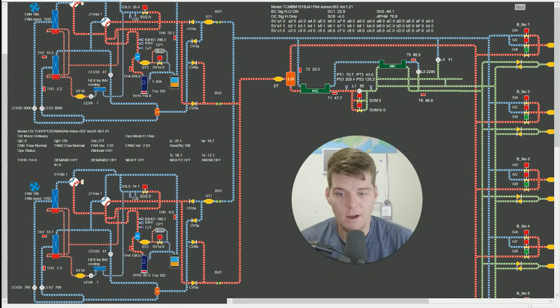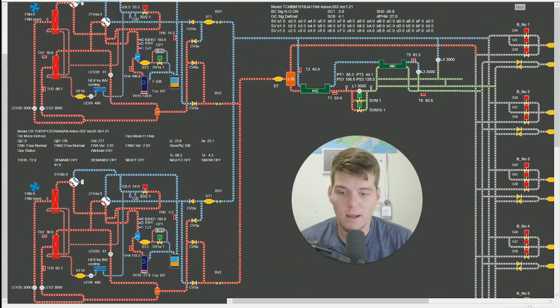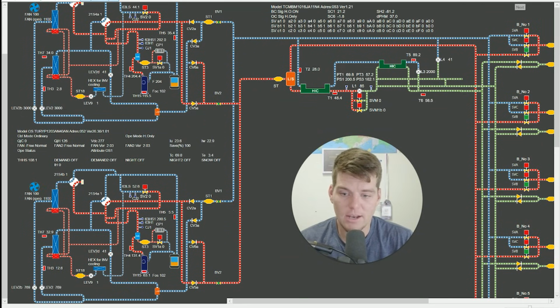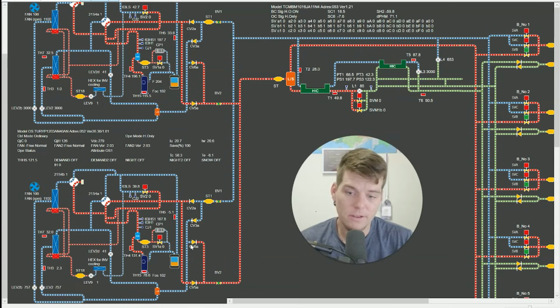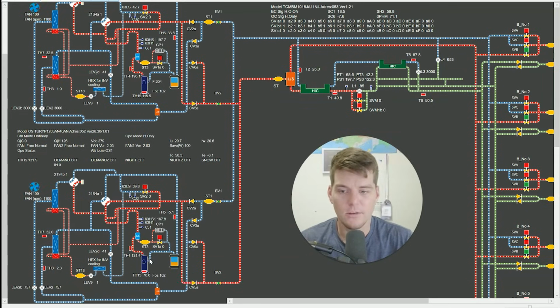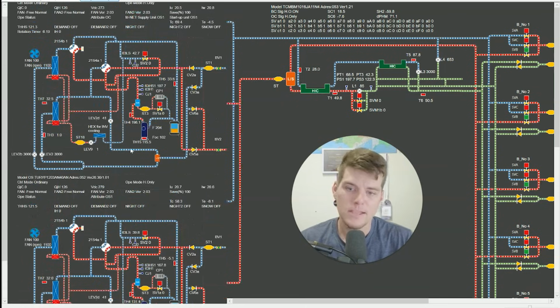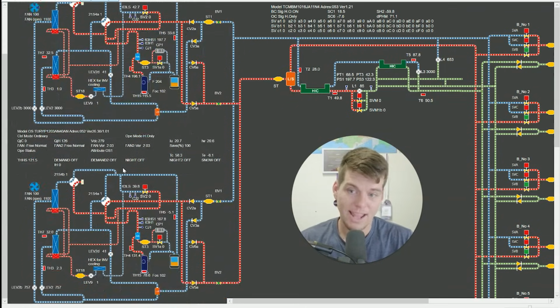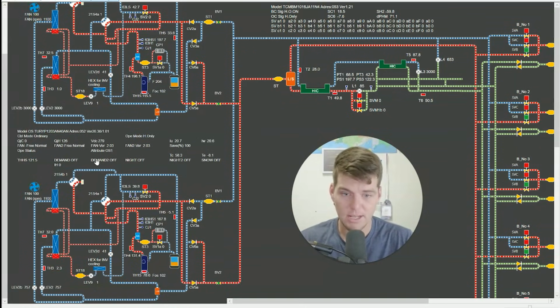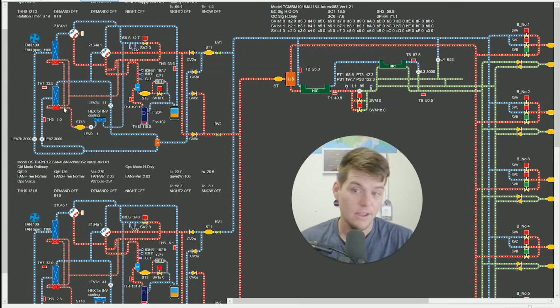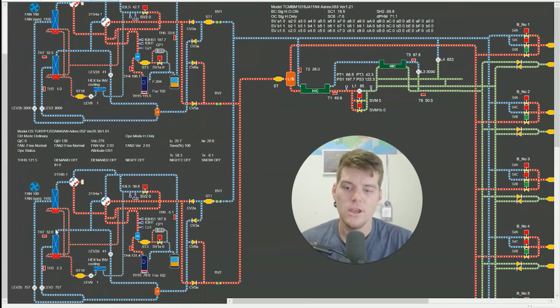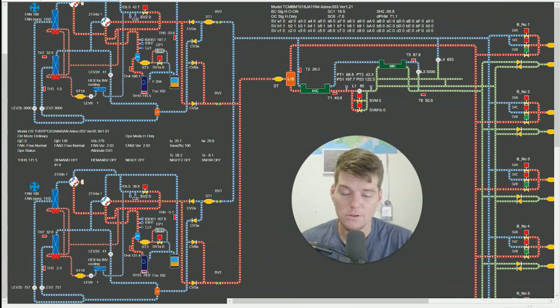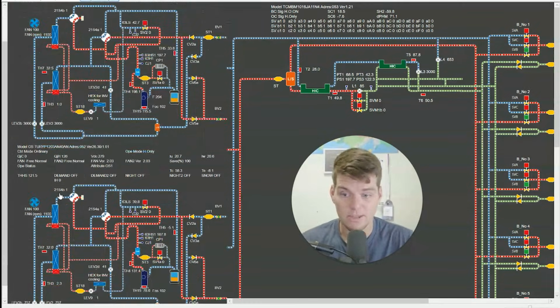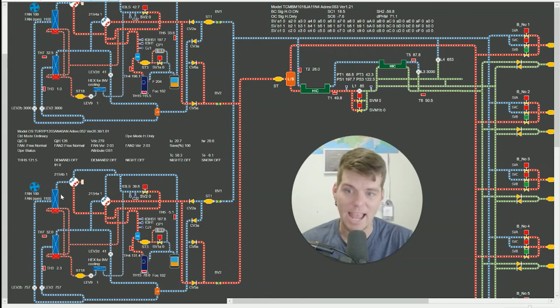Well, if I go and see how it floats over time, we notice it changes states, but then it goes back again, and it stays pretty much the same for most of this. But one thing we'll notice here, and this one's a very difficult one, in my opinion, to catch without a little bit of help and understanding and oversight, is that between these two compressors, we know they should be doing identical things, right? They're both in 100% heating mode, which means that they're both in an evaporative state, both upper and lower heat exchangers. For both of these systems, they're both in the same environment, close to the same ambient temperatures, right? Fan is running at the same speeds. They're doing the same exact thing.